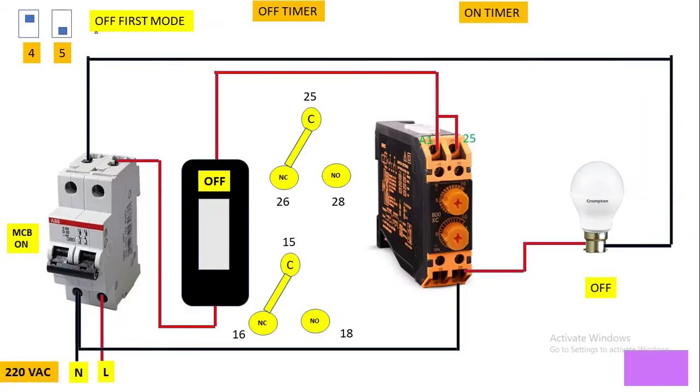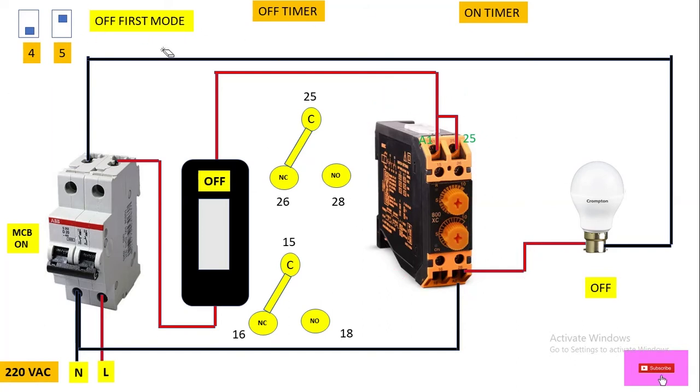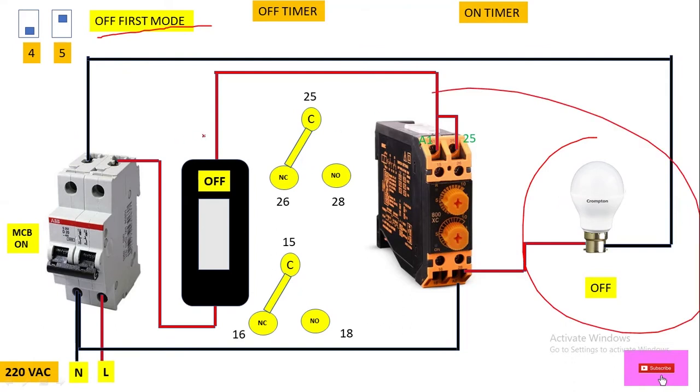First we will discuss off first mode. To operate this cyclic timer in off first mode we have to set the DIP switch. Here we have number 4 and number 5 DIP switches for mode setting. To set this cyclic timer in off first mode, we have to shift the number 4 DIP switch towards the downside and the number 5 DIP switch towards the upside. In this way we have set the cyclic timer in off first mode.